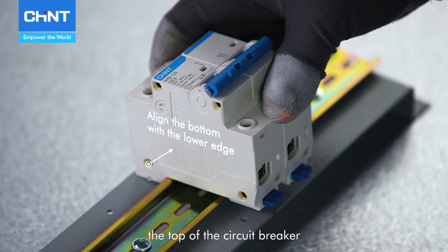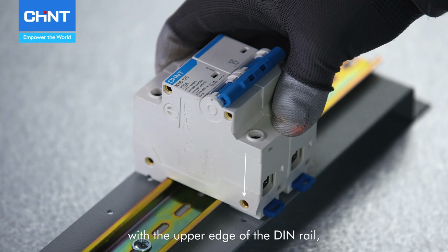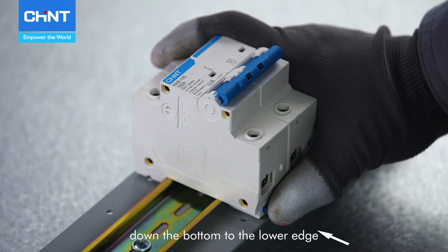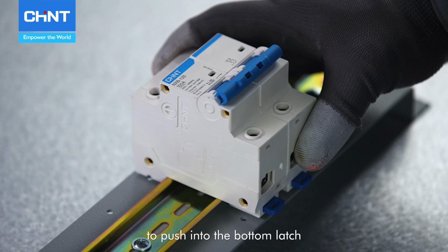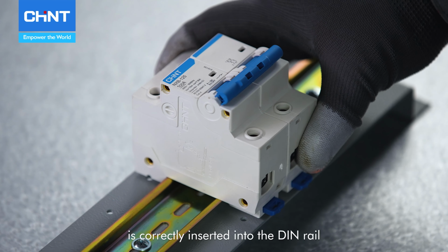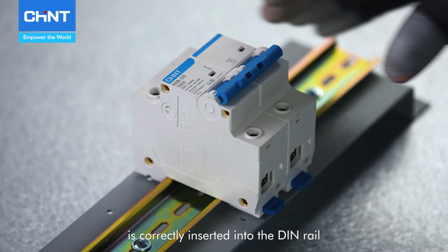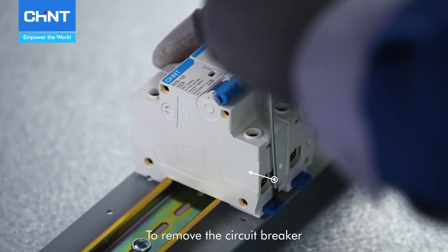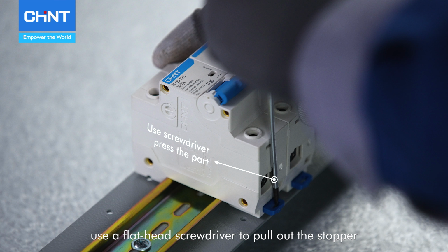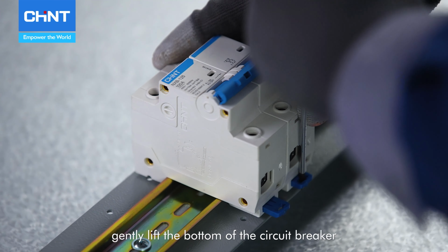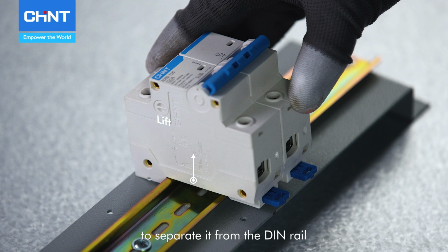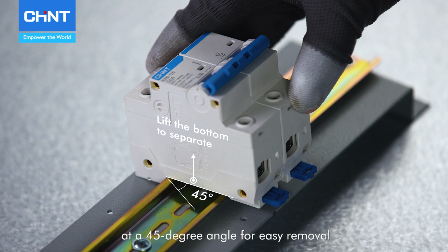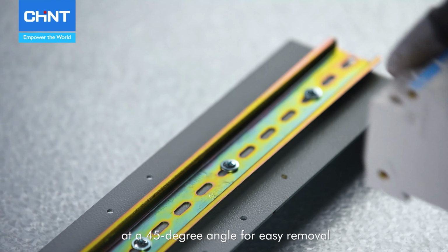Then align the top end of the circuit breaker with the upper edge of the DIN rail, and gently press down the bottom to the lower edge to push into the bottom latch, ensuring the circuit breaker is correctly inserted into the DIN rail. To remove the circuit breaker, use a flathead screwdriver to pull out the stopper. Gently lift the bottom of the circuit breaker to separate it from the DIN rail, and then slightly tilt it forward at a 45-degree angle for easy removal.